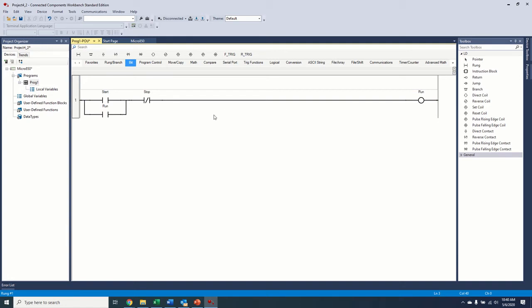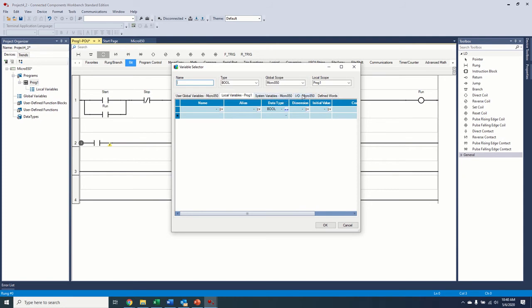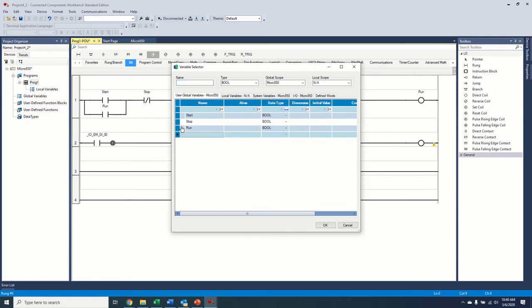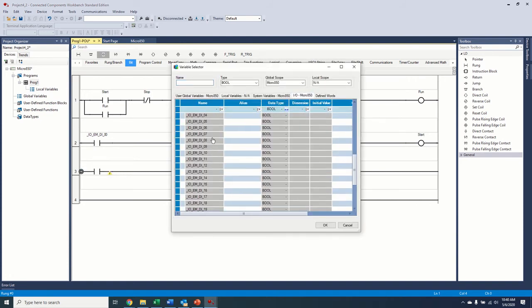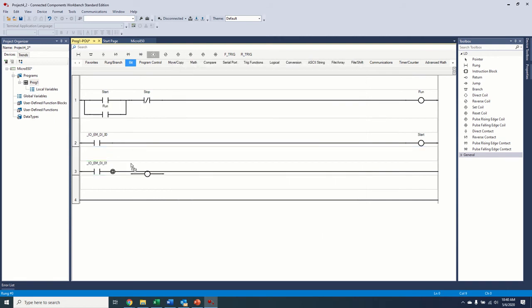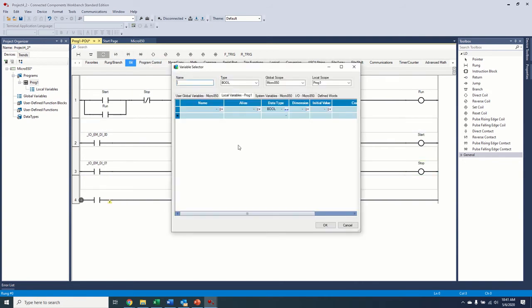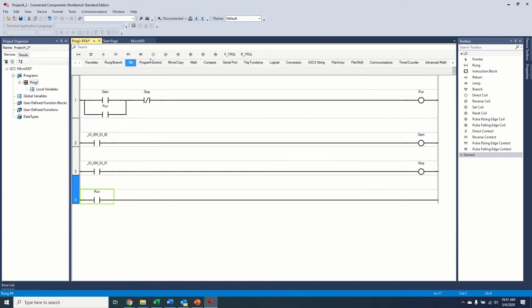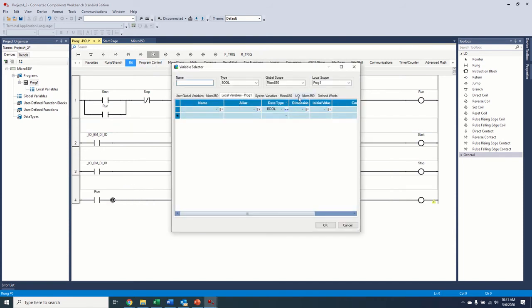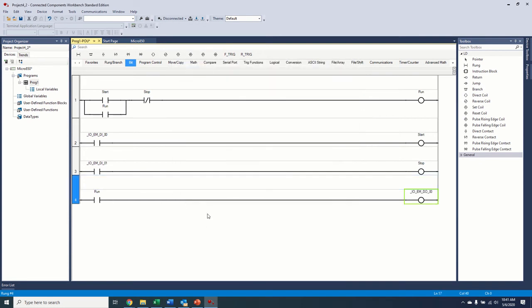So there we go, there's our starter. As you know, though, we're not tied to the outside world right now, so this program wouldn't do anything without some sort of outside input. So let's go ahead and add a few rungs here to tie our embedded IO, which is right here, our IO and our micro 850, digital input 0 to turn on our start. And then we're going to put in digital input 01 to turn on our stop. And then we're going to do our run command, turn on an output, just use the output 0. So there we go, simple motor starter.